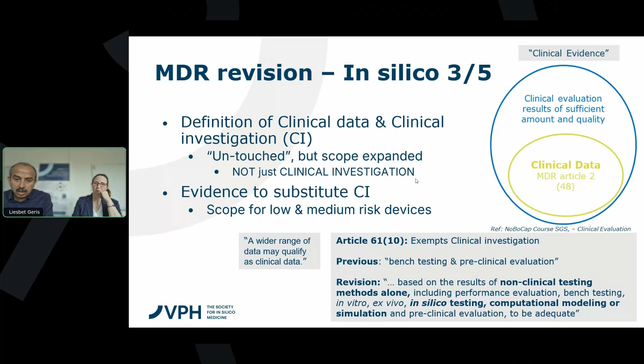They acknowledge that doing clinical trials for low and medium risk devices is going to be expensive, not always necessary, and we may be able to substitute that evidence with other sources of evidence, and that's where they acknowledge in silico as a clear player. For example, I just point to Article 61(10) because this is a specific article that points to those pathways that don't require clinical investigation. Previously, it was listed that bench testing and preclinical evaluation can be accounted as an evidence source, but now in the revision text, especially the last line, you can see that it spells out explicitly that in vitro, ex vivo, in silico testing are evidence sources that they could consider for Article 61(10), where conventional clinical investigation involving physical trials can be substituted through alternative sources of evidence.